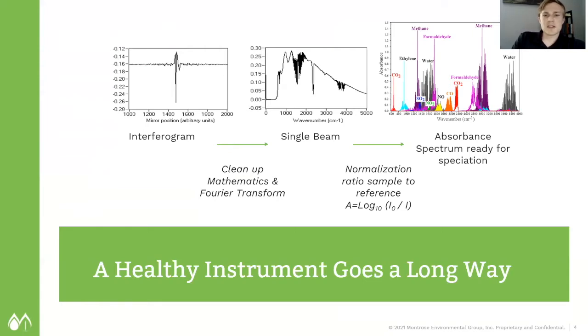If you have impacts to your single beam, and in this case with this instrument the single beam is actually not all that strong. We like to see, out of the box, that single beam strength, we measure right around 2,500 wave number, should be more or less around 1 or a little greater than 1, hopefully. The better the signal, the better your signal to noise, the lower your detection, and the better your resolution.